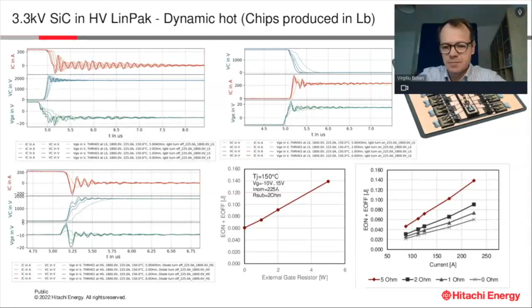Silicon carbide, this is the 3.3 kilovolt that I showed in the previous slides, but one of the promises of silicon carbide is also higher voltages. We are also developing a 6.5 kilovolt silicon carbide, thinking of traction application, but more in the direction of grid, where there's a lot of series connection of IGBTs nowadays, and this will profit a lot if we have per semiconductor a much higher blocking voltage. So that's why we look a lot at higher blocking voltages, like 6.5 kilovolt.